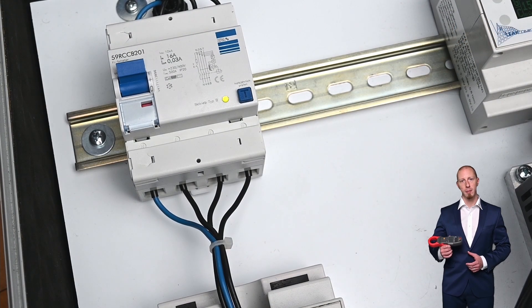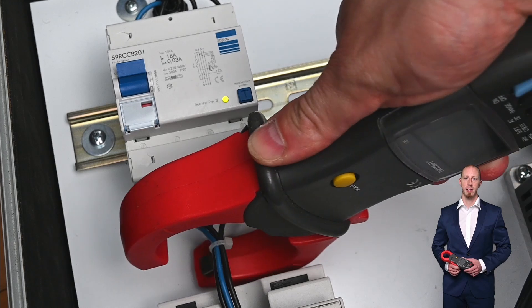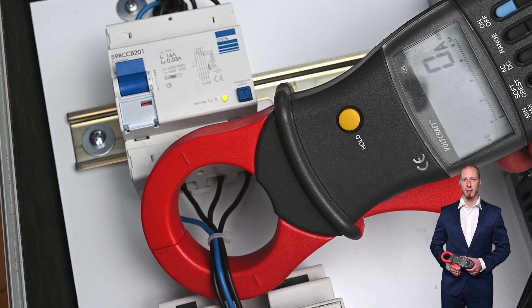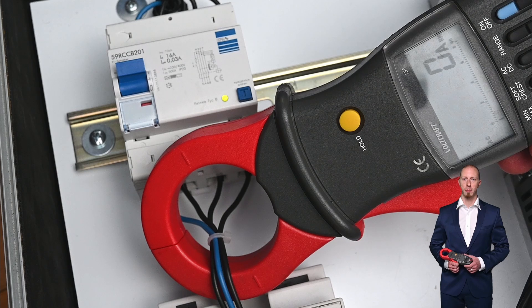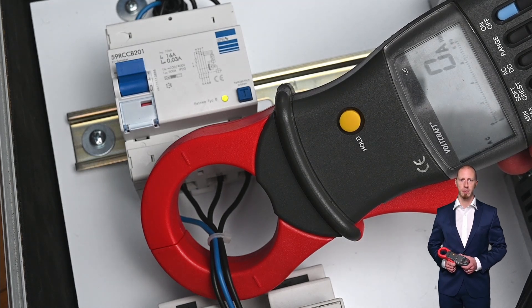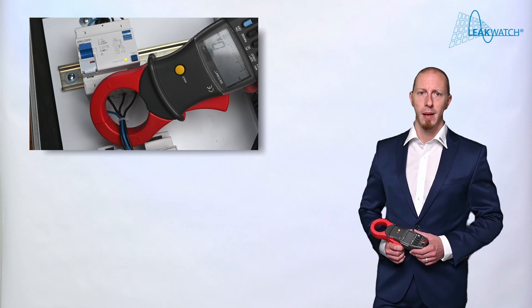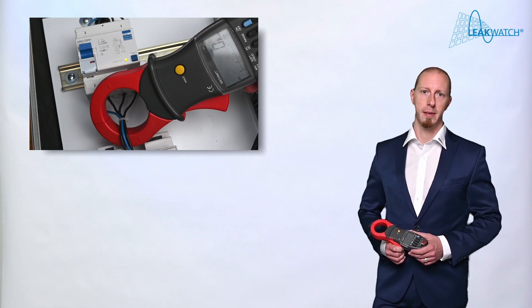Many people know how to measure the leakage current in the residual current measuring method. You take a clamp amp meter or a leakage clamp and lead the phases and the neutral conductor, in short, the outer conductors through, and you can read the leakage current on the display. Right? Yes and no. In principle, the type of measurement is correct.